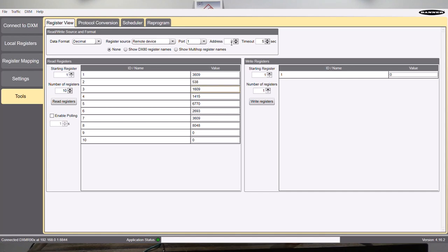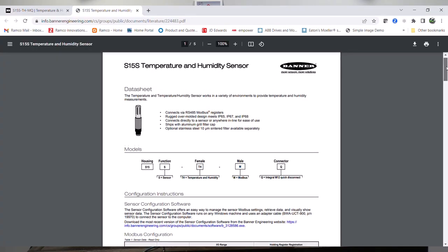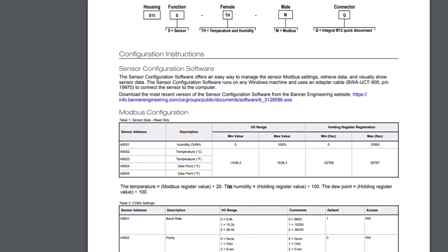So what I'm going to do is look at the remote registers and we're going to look at the first actually seven registers. And the reason I know that is if I go to the data sheet for the temperature humidity sensor, I'm always going to scroll down and look for the Modbus configuration. So the Modbus devices start at 40,001 through in this particular case to 40,005. So you're going to see everything from humidity, temperature and dew point on this particular sensor.